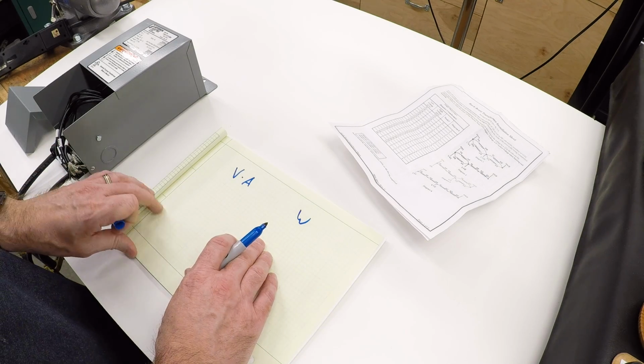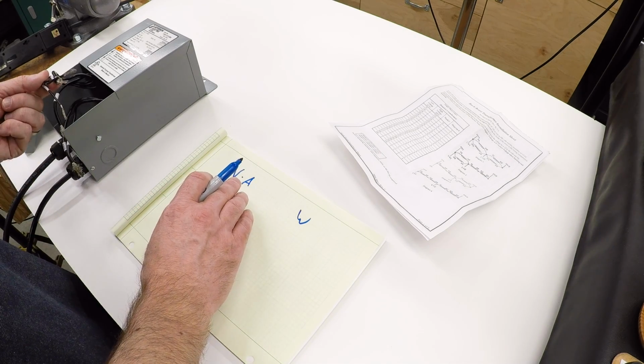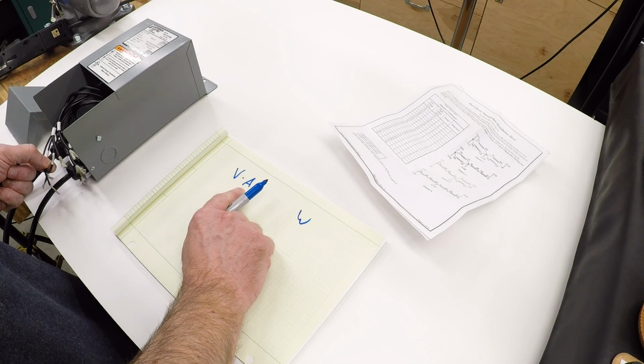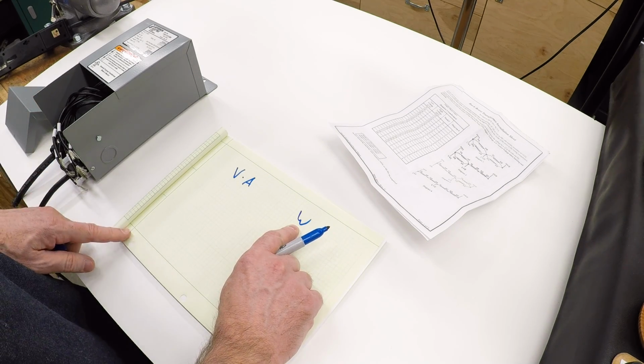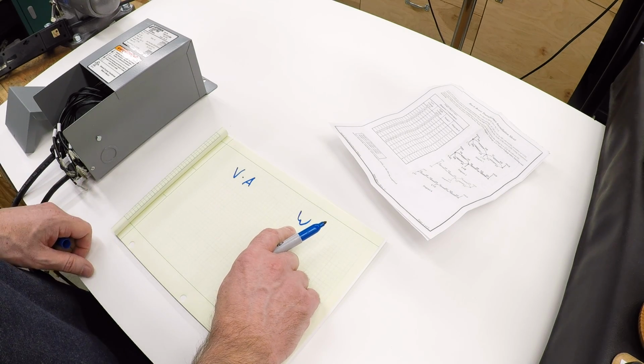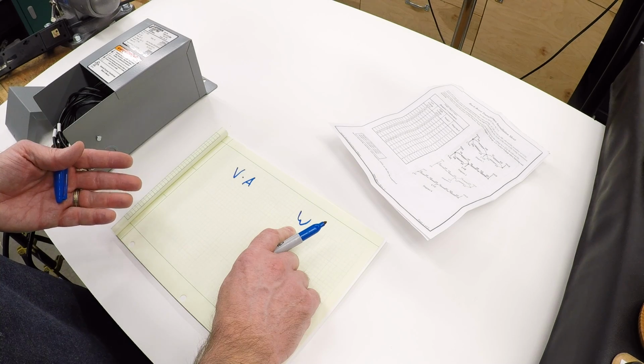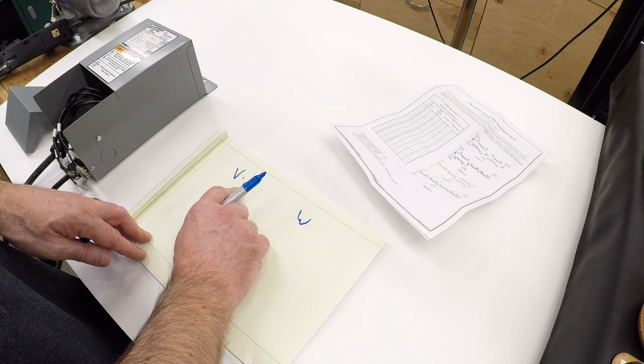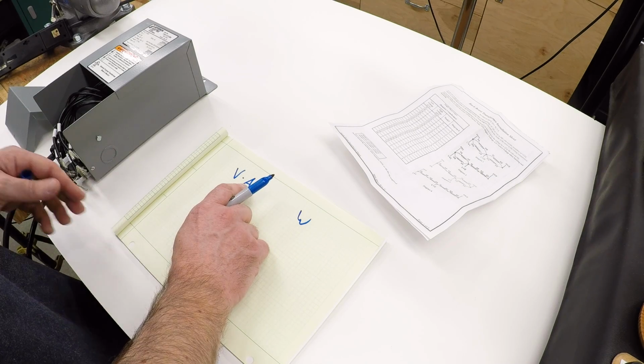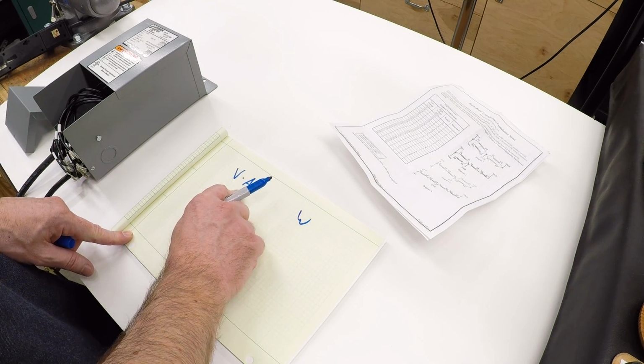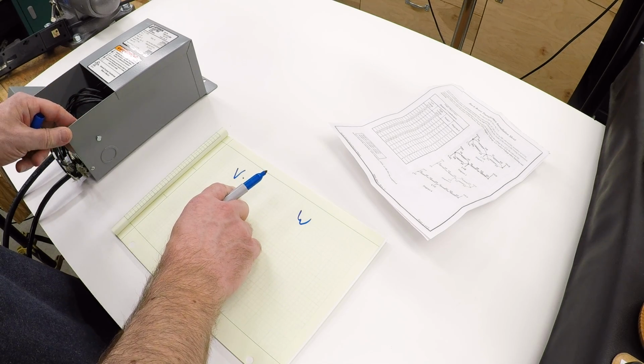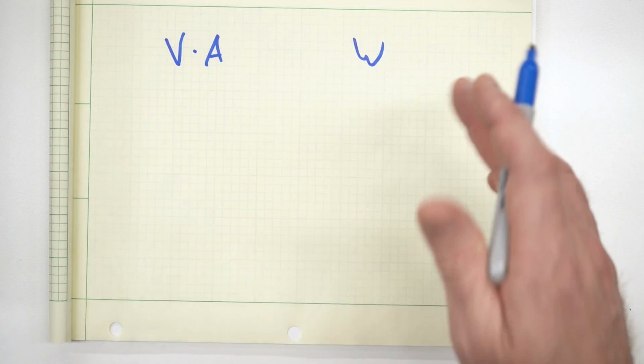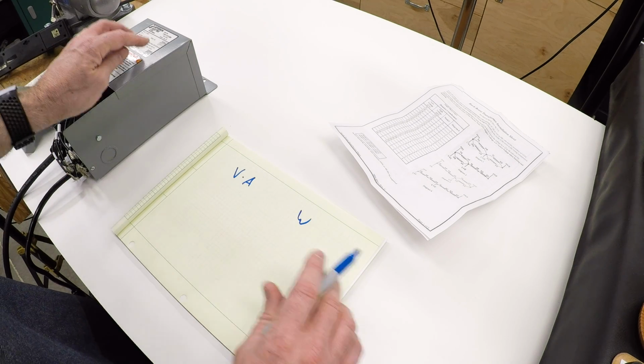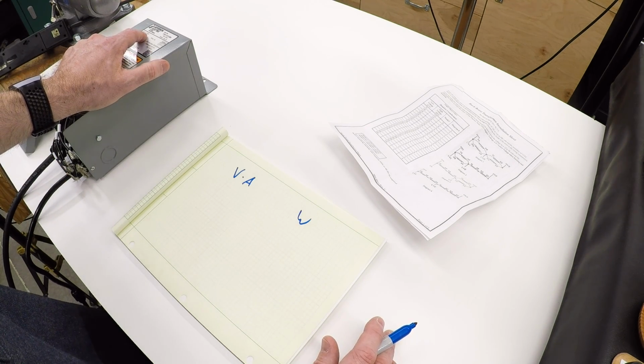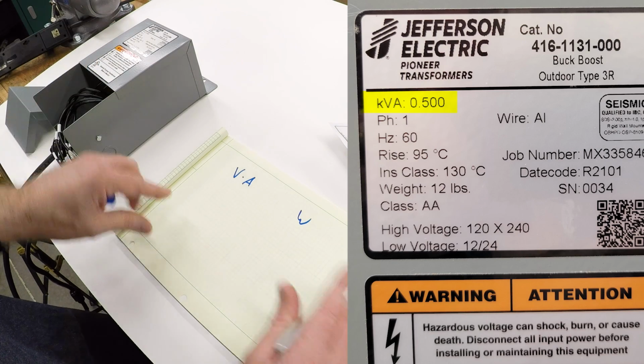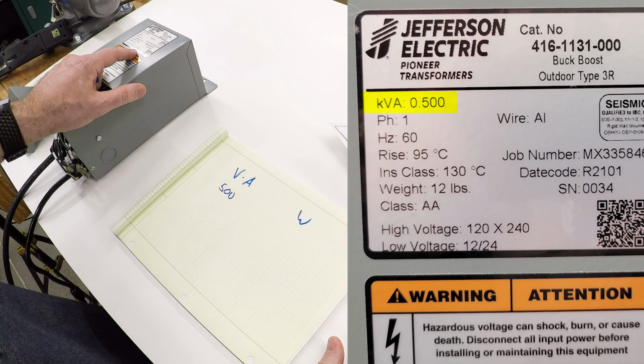This matters because wires need to be sized to handle the current in amps. If you need 100 watts of power, but because of a low power factor you actually need enough current to support 200 VA, you now need twice as much copper in your electrical distribution system and your device to support that. So let's talk about what that means for sizing a transformer -- this is a 0.5 kVA, or 500 VA transformer.